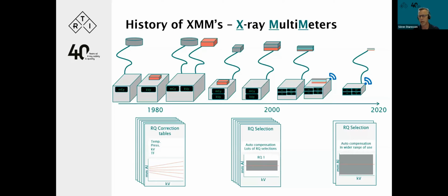Throughout the time, we come to the multi-sensors around year 2000, the 1990s. The meter started to self-compensate the values. You still had to select quite a lot of different radiation qualities, which you still have to do, but those have become less and less, and the meters cover a broader and broader use. Coming back to XMMs, X-ray multimeters, what we mean with that is a meter that measures not only dose or not only kV, but both parameters, and possibly together also with half value layer and total filtration.